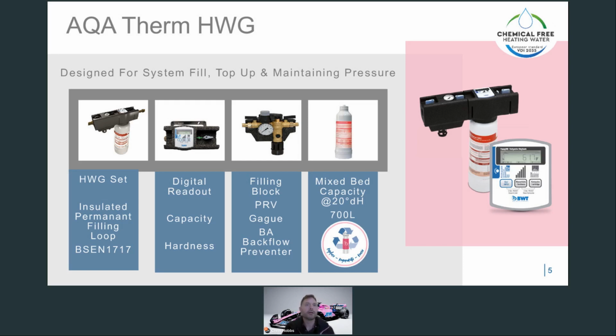So our products: we have two types of systems to demineralize water to VDI 2035 specification. This is our AQA Therm. It's used for smaller systems or to top up larger systems and maintain their pressure, useful for keeping oxygen out of a leaky system. These products are designed to be left in place. It's compatible with BS EN 1717, so it can be fitted as a permanent filling loop. You can see from these pictures it's insulated to protect it from damage and also from condensation.